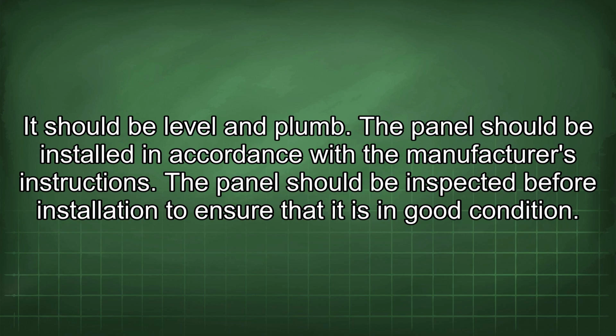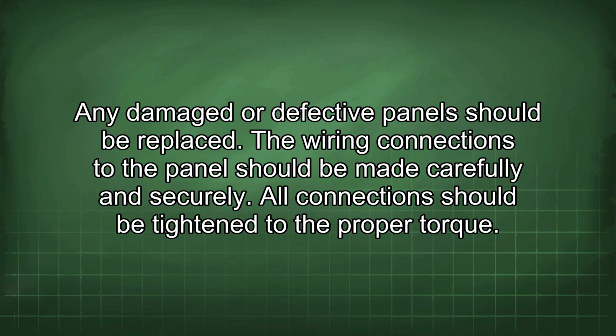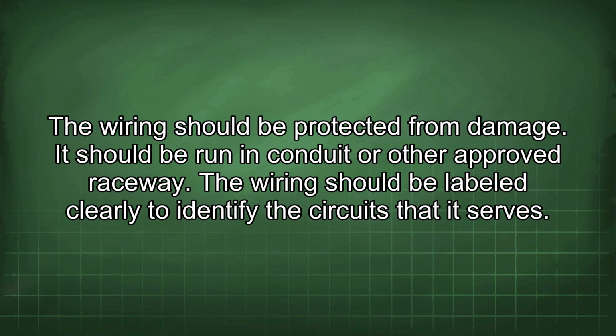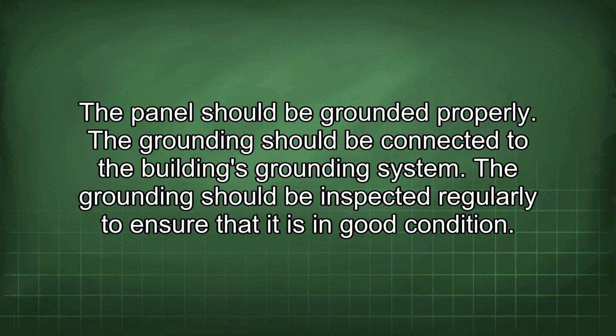The panel should be inspected before installation to ensure that it is in good condition. Any damaged or defective panels should be replaced. The wiring connections to the panel should be made carefully and securely. All connections should be tightened to the proper torque. The wiring should be protected from damage. It should be run in conduit or other approved raceway. The wiring should be labeled clearly to identify the circuits that it serves. The panel should be grounded properly. The grounding should be connected to the building's grounding system. The grounding should be inspected regularly to ensure that it is in good condition.